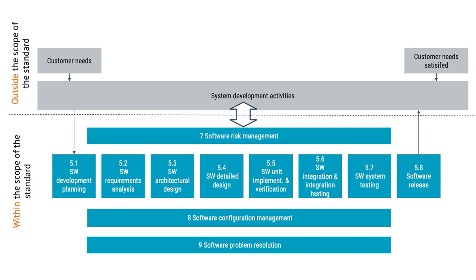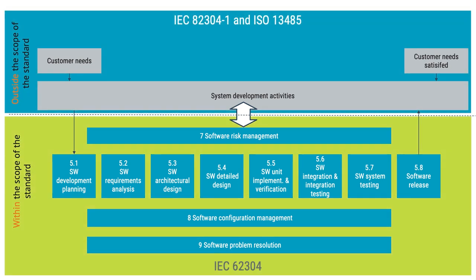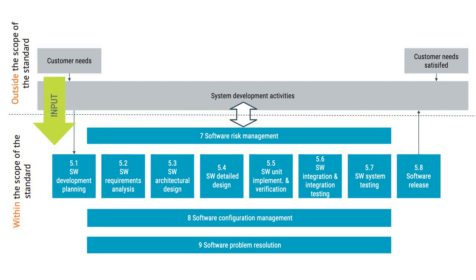This graphical overview visualizes the scope of IEC 62304. Blue boxes are in scope; gray are out of scope. The arrows between blue and gray indicate where there is an information exchange. IEC 62304 gets its input from IEC 82304-1 and ISO 13485. The first arrow gives you inputs about what and when — when includes pre-releases for various purposes before the final release. What can be functional requirements such as information to display on a screen or alarm management, or hardware constraints — for example, whether you have one or more CPUs available, or if communications should happen over USB or Ethernet.